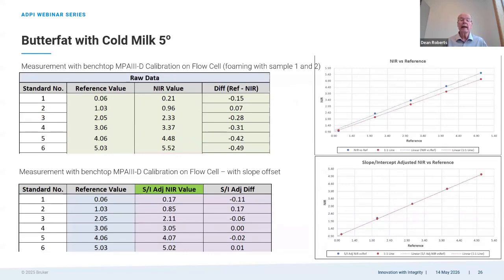Here's what we got at the 5 degrees C, and then applying the slope and offset. You see really the same relationship that we had with the 40 degrees C after the slope and offset correction is applied. Could we do a little bit better on that? Maybe, but really it's only the 2% sample that's off, and there may be some residual impact from the foaming that hasn't been completely emulsified by the higher fat levels. Next slide.